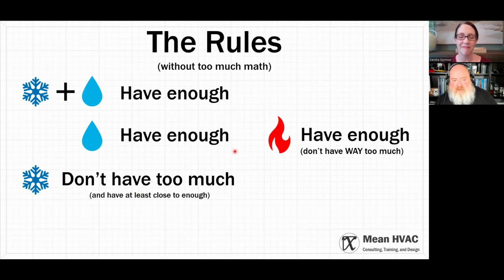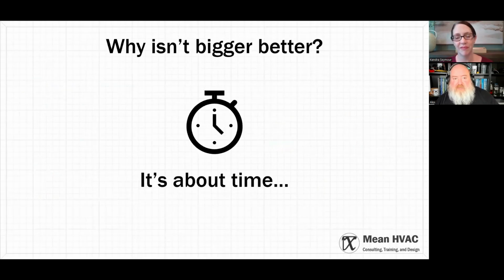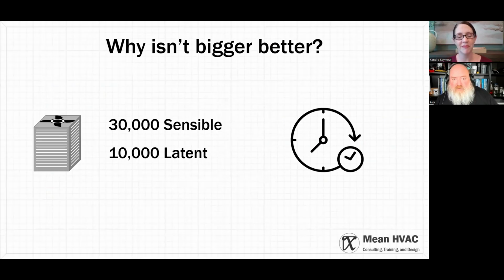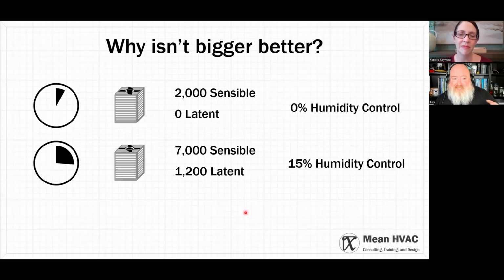Heating is easier, just don't have way too much. Bigger's not better here either, but it's less harmful because it's about time. When you run a system that has a bunch of ability to control the temperature, it will control the temperature. When we look at the ratings of a system, this is for when it runs for an hour. I get 30,000 sensible and 10,000 latent if it runs the whole time. BTUs are per hour, so the thing has to run for an hour for it to do that. And the refrigerant cycle is a cycle. When it turns on, it's not instantly as cold as it's going to get and as efficient as it's going to get, so maybe the first 5-10 minutes, it does no humidity control.